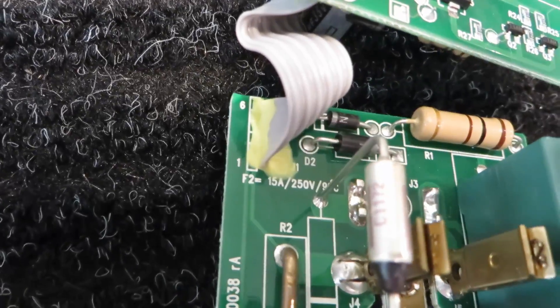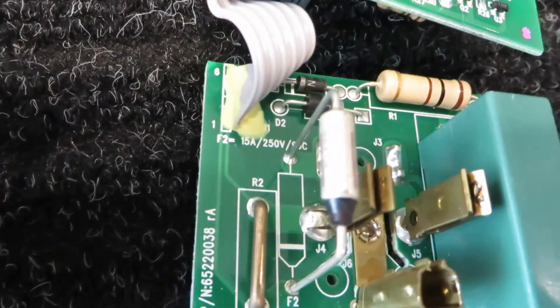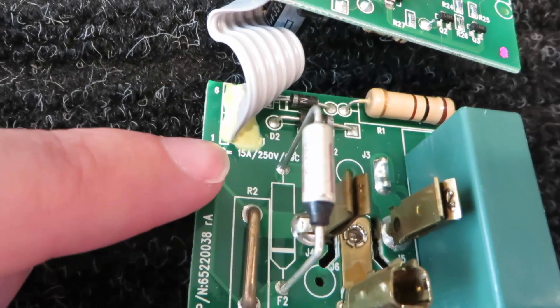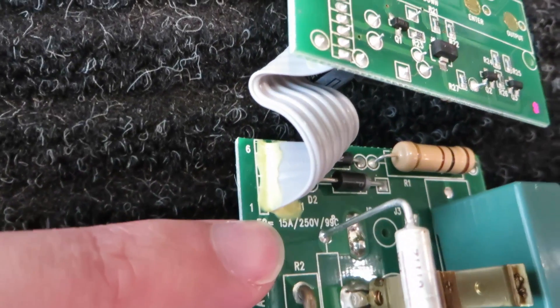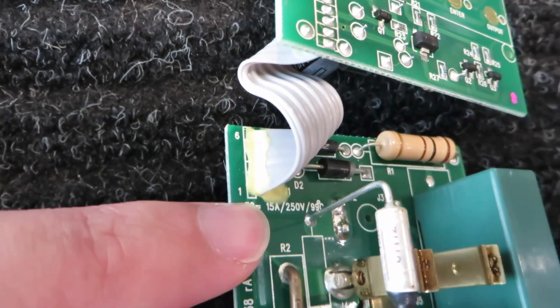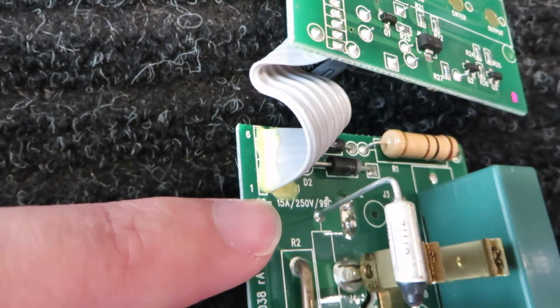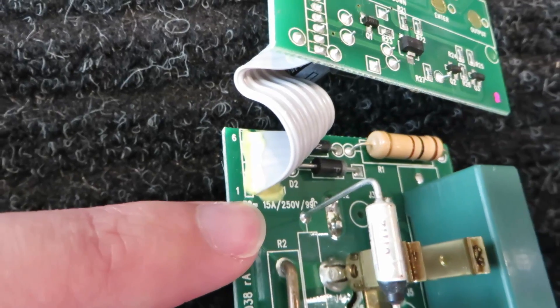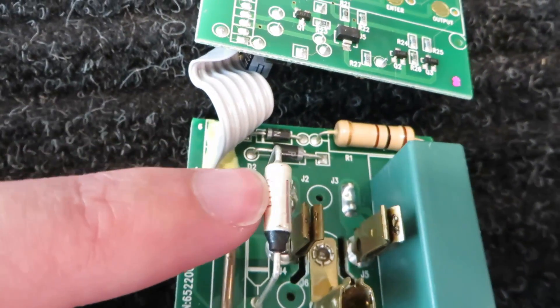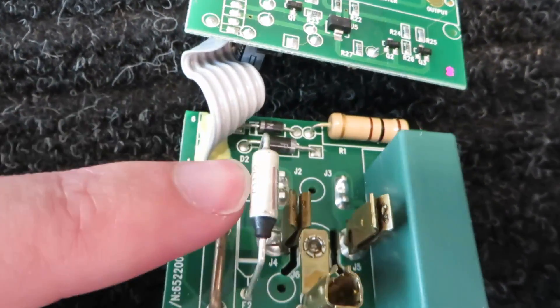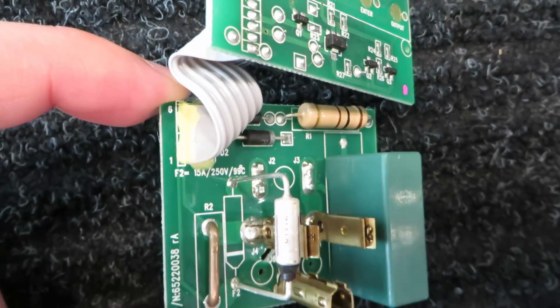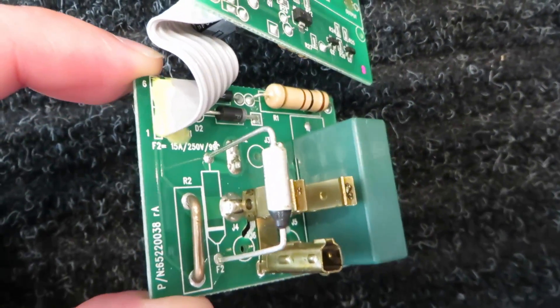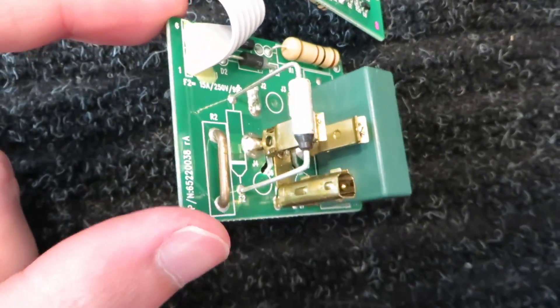A couple of notes of things that I find to be interesting. This particular fuse is a 15 amp fuse, 250 volt rated, and 99 degrees Celsius. So that means that it should trip at 99 Celsius and reset when it gets cold. It's obviously not resetting. So this thing failed. Maybe it's because the overload was so severe that it heated up too quickly, or maybe it's just cheap. I'm not quite sure.